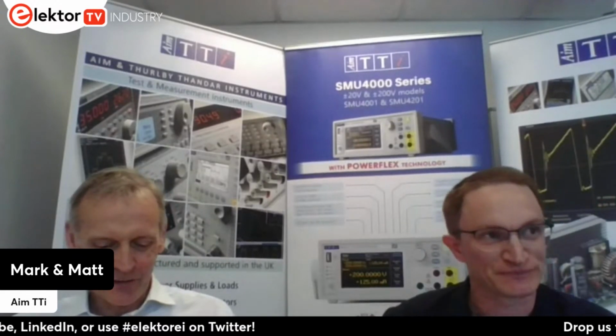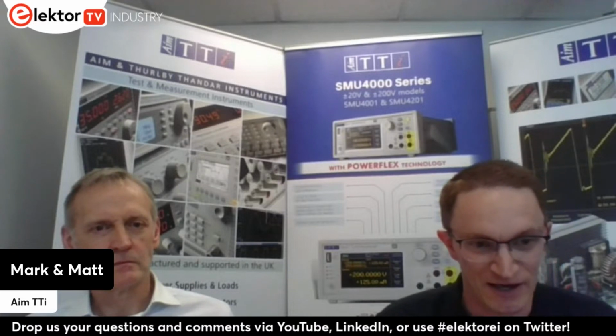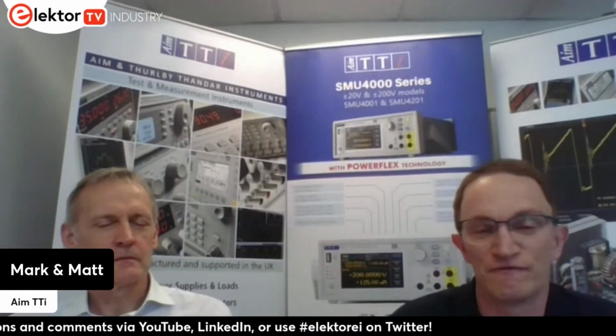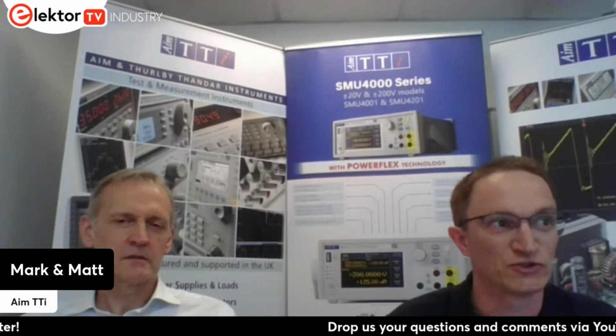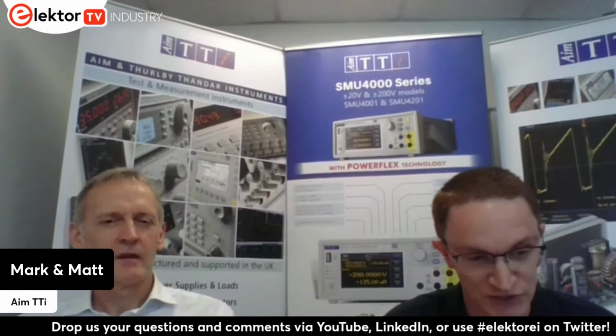Yeah, so really, the primary things you might be looking at are materials testing and characterization. You might be looking at battery testing. An SMU is a great instrument for battery testing because it's important for everyone to note that this is a 4-quadrant instrument. For those that aren't aware what that is, basically it means it can source and sink. So you can source positive voltages or positive currents and negative currents and voltages. So for battery testing, it's a real benefit because you can not only charge a battery under test, but you can also discharge that battery with one instrument under the same test conditions.